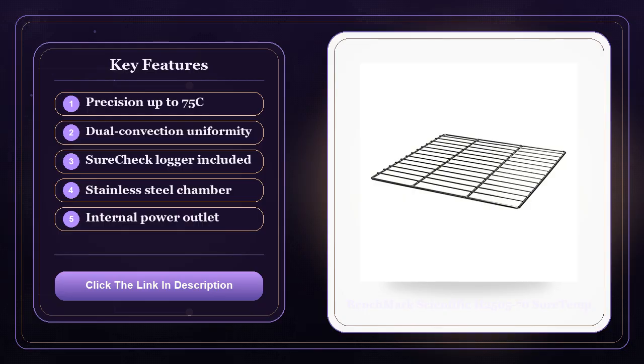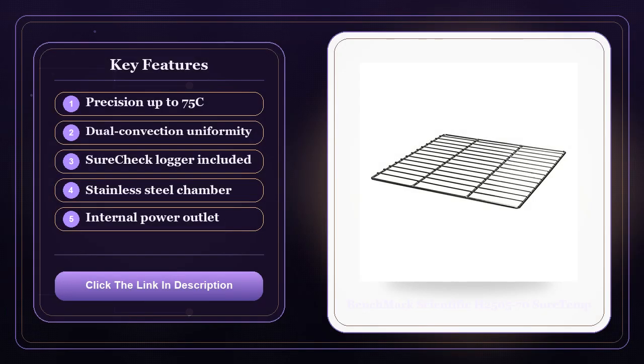In practice, that matters when you're running a 96-well plate, and you can't afford a few wells sitting a degree hotter or cooler than the rest. Those tiny variations can skew assay results and force you to repeat experiments. The fact that the system also advertises rapid recovery after door openings means you won't spend a half-hour waiting for the chamber to settle before you resume work, which is a genuine time saver in busy labs.